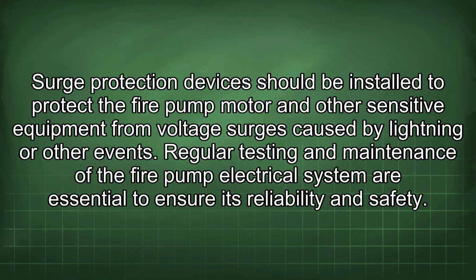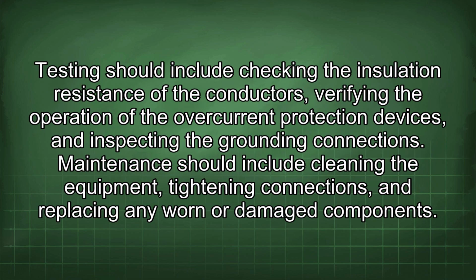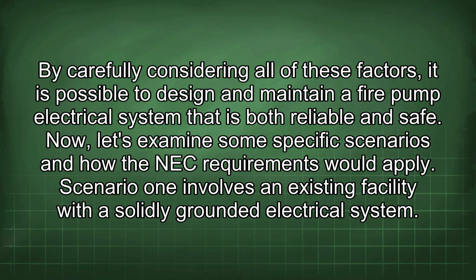Regular testing and maintenance of the fire pump electrical system are essential to ensure its reliability and safety. Testing should include checking the insulation resistance of the conductors, verifying the operation of the overcurrent protection devices, and inspecting the grounding connections. Maintenance should include cleaning the equipment, tightening connections, and replacing any worn or damaged components. By carefully considering all of these factors, it is possible to design and maintain a fire pump electrical system that is both reliable and safe.